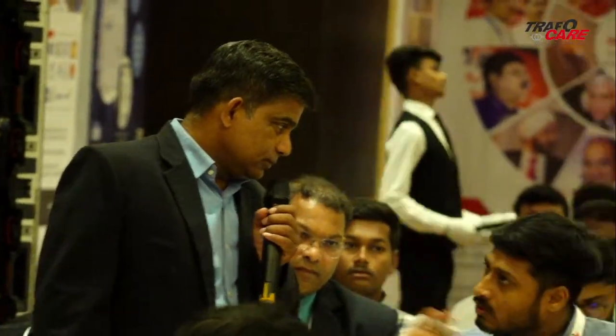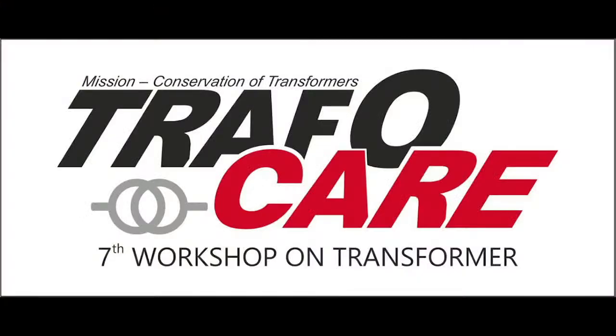Maybe Dr. Narasimhan, can you take this question: the frequency of the oil filtration, and second, shall he go for oil filtration or not? That's his question. And all test reports and the parameters are within limit. Dr. Narasimhan. No, he's asking on OLTC or overall. No, he has a transformer. He's from ONGC. Transformer is from 2012. They tested the parameters of oil. All are within limit and very well in the required values. So, does he need to go for filtration? If yes, what should be the frequency? So that's the reason I pass the question on to Mr. Narasimhan.